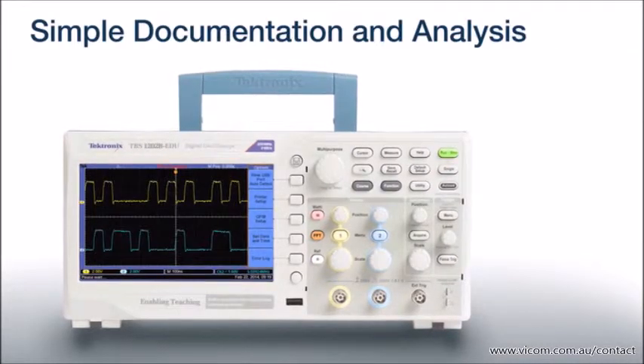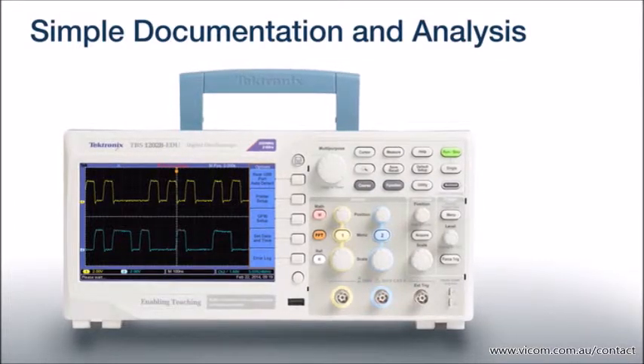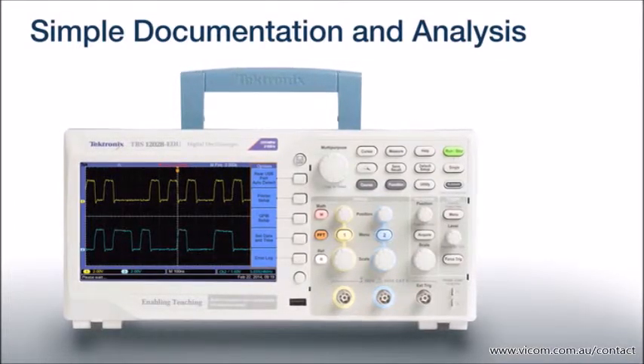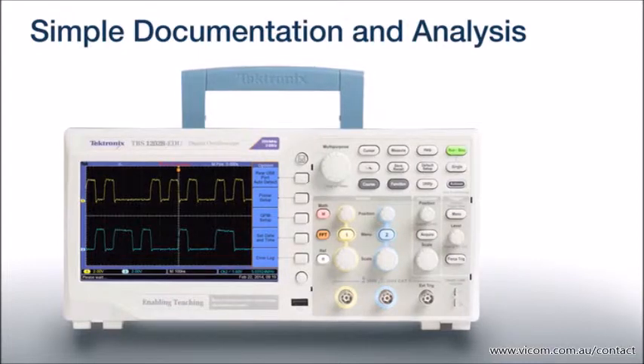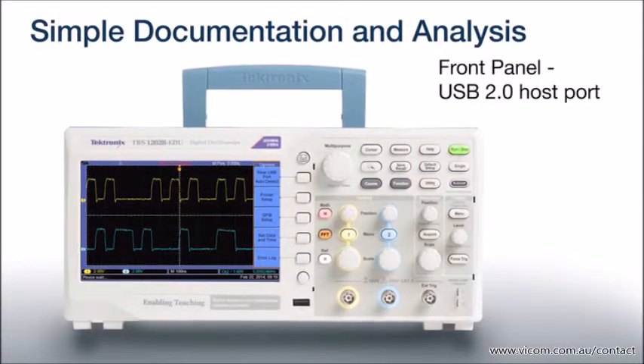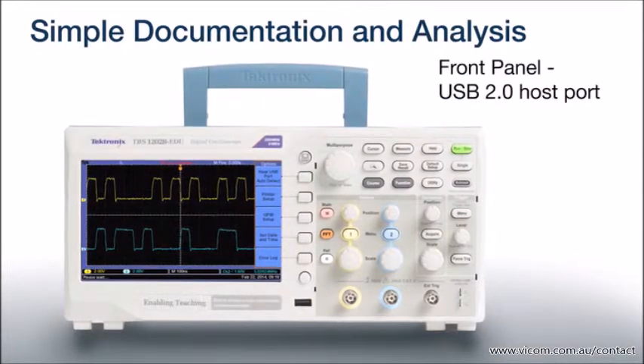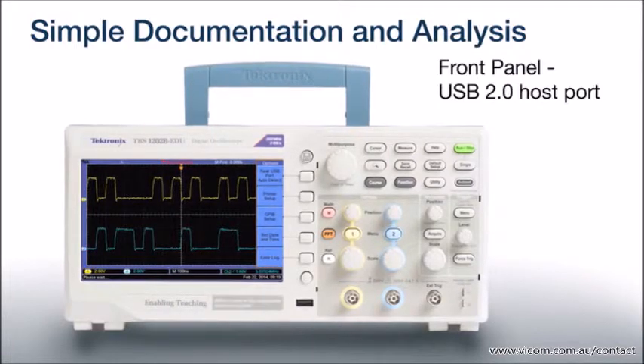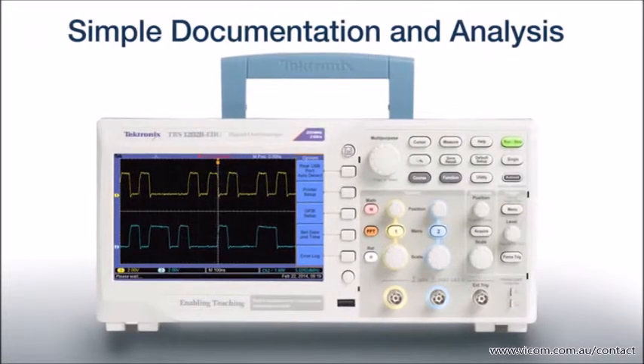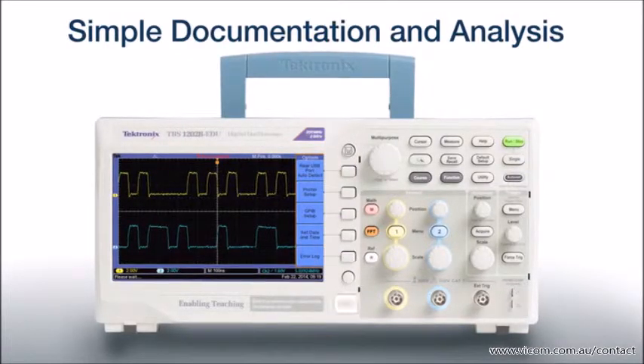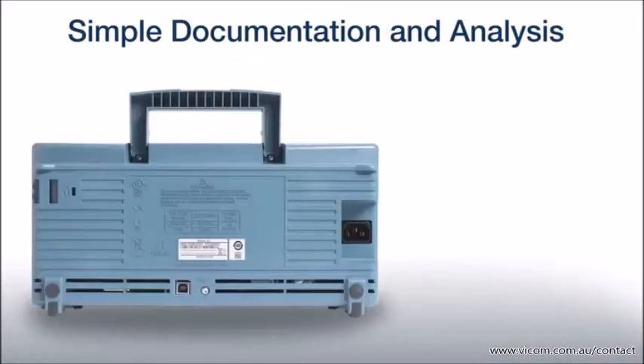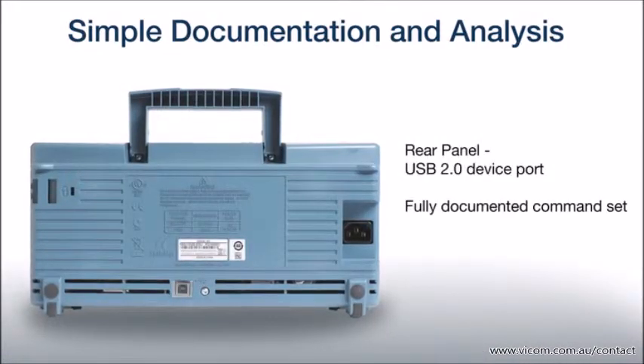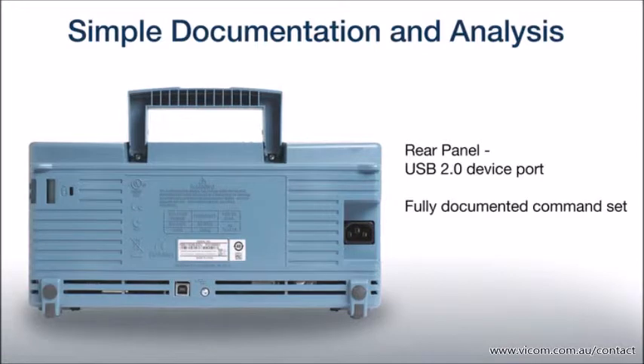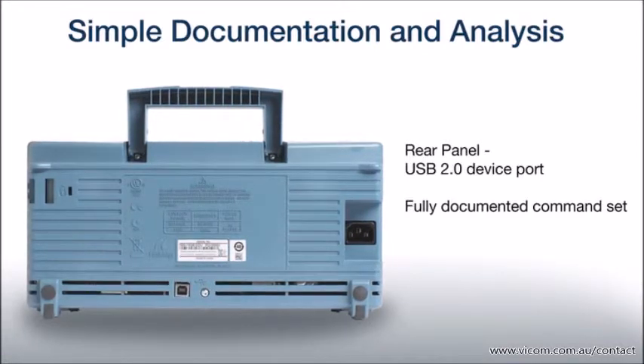Some value-priced oscilloscopes make you give up data handling and remote control capabilities. Not the TBS1000B-EDU. It supports easy data transfer and a fully documented command set for remote control. Just one button push saves your waveform or setup data to a flash drive plugged into the front panel USB host port. A back panel USB device port is backed by a comprehensive set of commands for PC control.